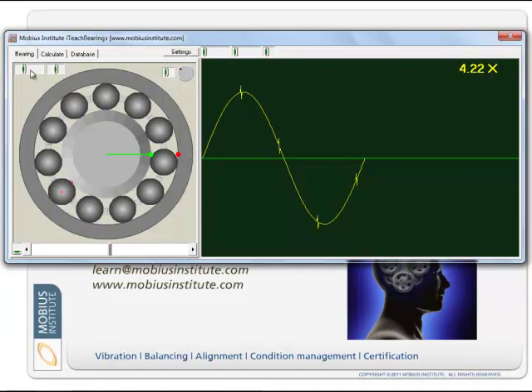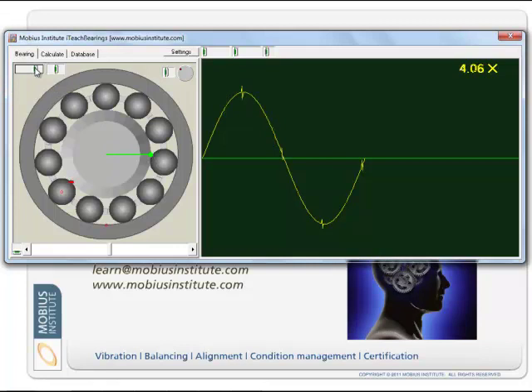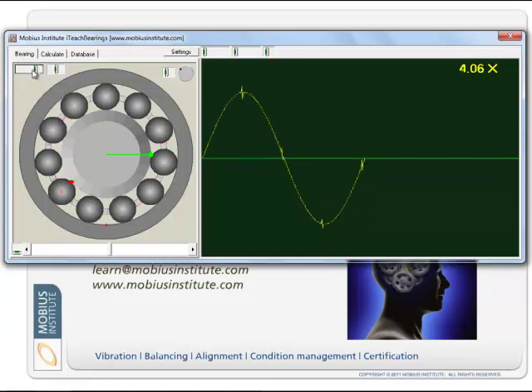And that's why the defect frequency for this bearing for the outer race fault is 4.22 times the running speed. We can go through and look at a fault on the inner race — it's actually under that green dot there. So we just saw outer race; this is inner race; this is a fault on the ball; and this is a point on the cage itself.